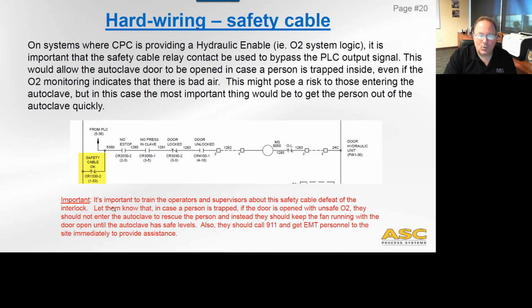interlocks. And when that happens, though, and again, you need to know this as a controls engineer and train on it. It's important to train operators and supervisors about this safety cable defeat of the interlock. And that's called defeating the interlock because there's an interlock for O2, but this defeats it. Let them know that in case a person is trapped, the door will be allowed to be opened with unsafe O2, but that they shouldn't enter the autoclave to rescue the person until they get safe oxygen or they have, let's say, a fire department shows up with a respirator. Because what we don't want is to have one person in the autoclave with bad air and then someone goes in and they faint or drop dead because of lack of oxygen.